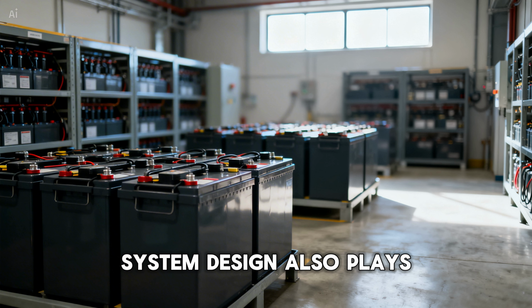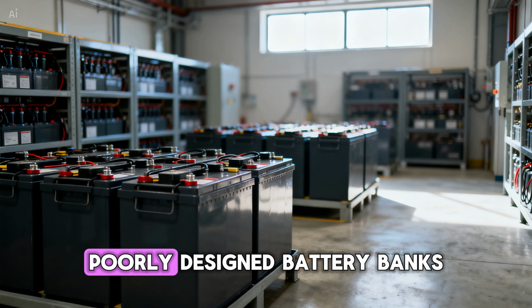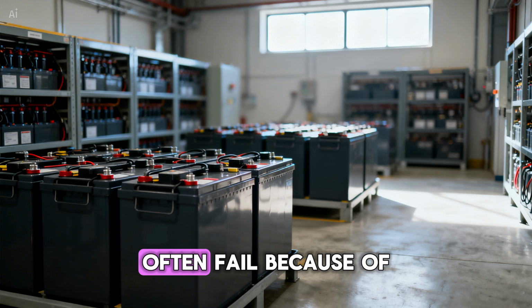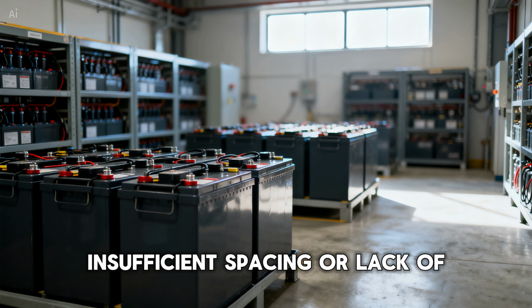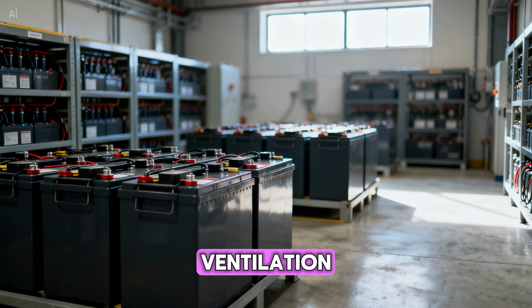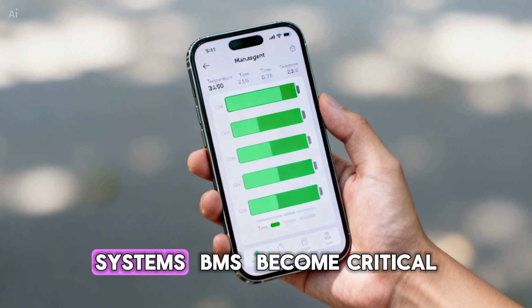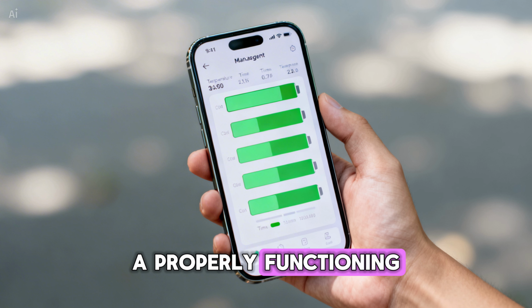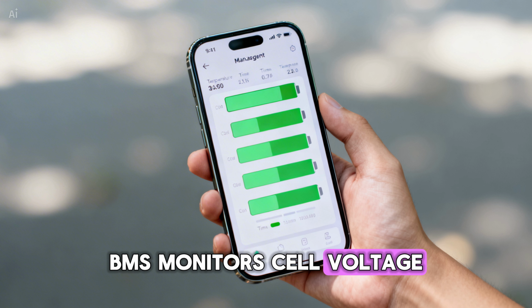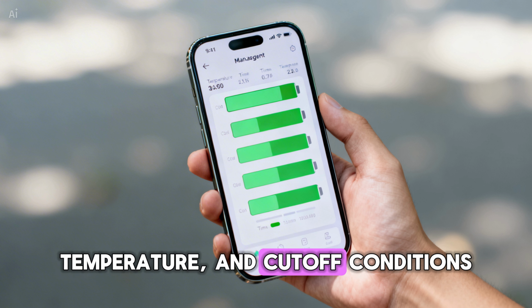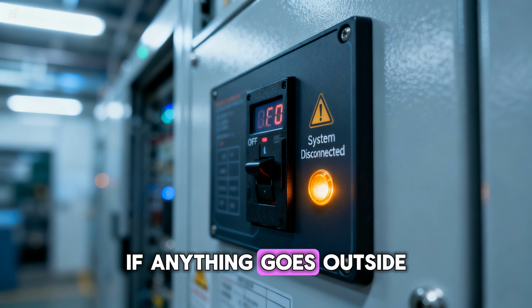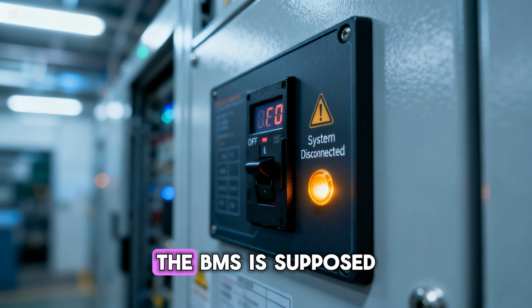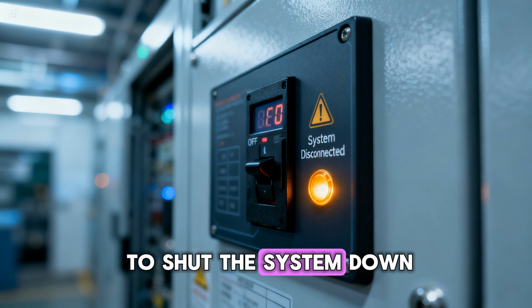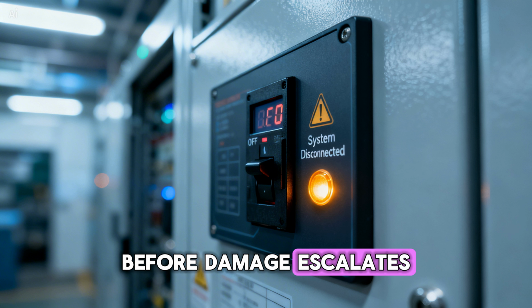System design also plays a huge role. Poorly designed battery banks often fail because of insufficient spacing or lack of ventilation. This is where battery management systems, BMS, become critical. A properly functioning BMS monitors cell voltage, temperature, and cutoff conditions. If anything goes outside safe limits, the BMS is supposed to shut the system down before damage escalates.